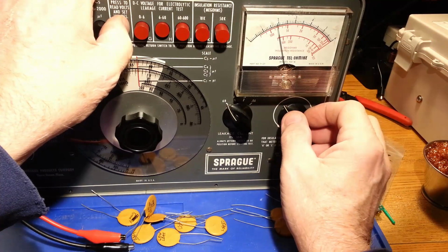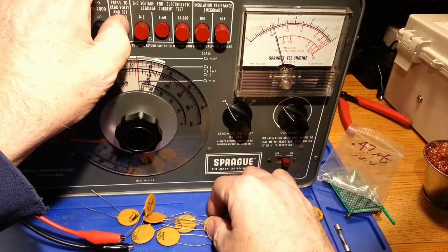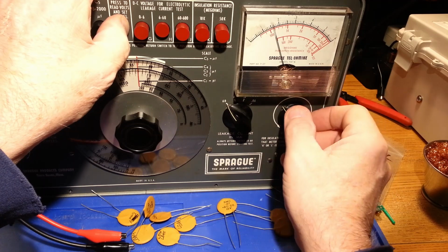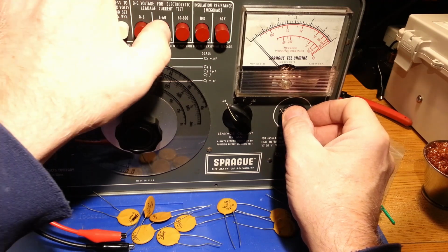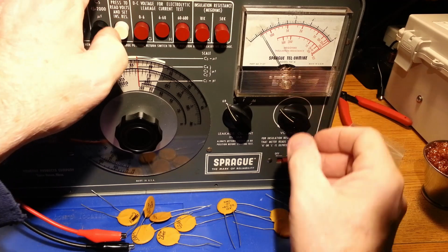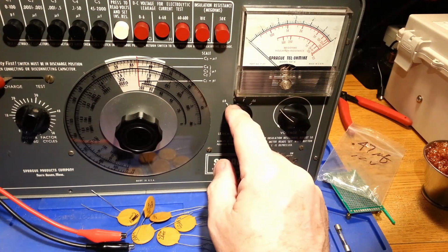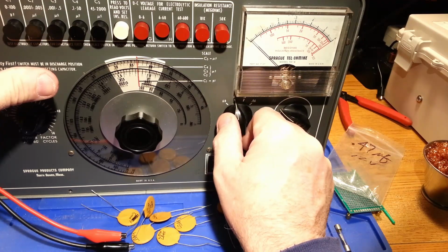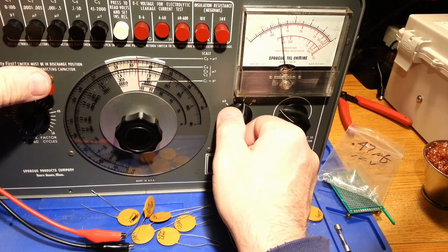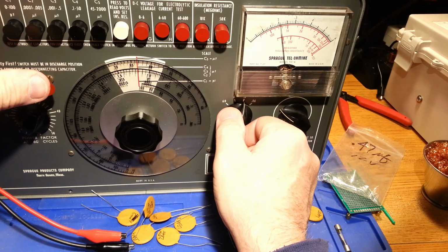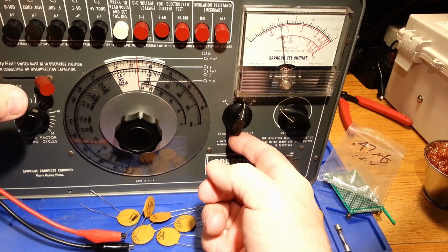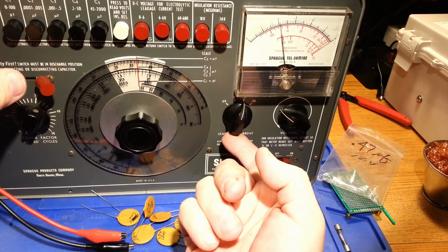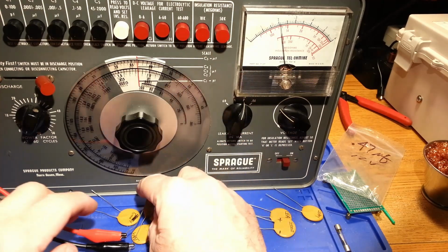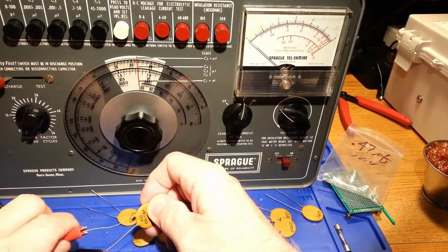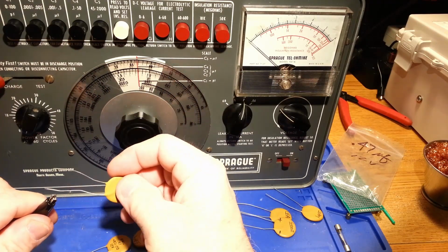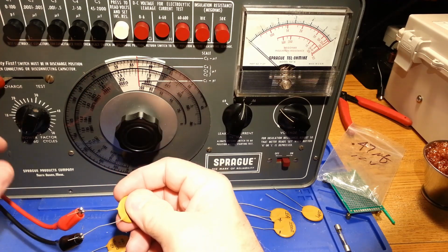In this case, I have to use the calibration button. It's a 12 volt. So I've got my 0 to 60, my calibration voltage for 12 volts. Meter indicates 60 milliamps. That's a 0.6 milliamp full deflection, so that's about a 0.2. I'm going to go with, should be a good one.